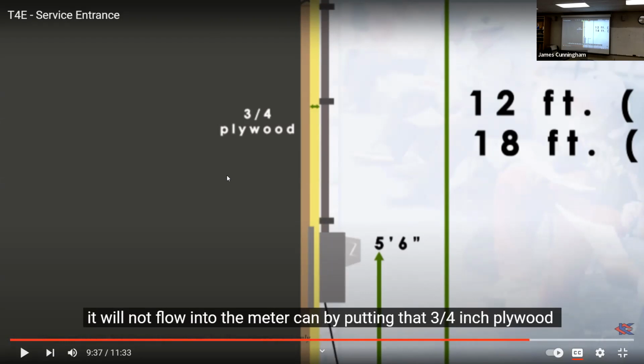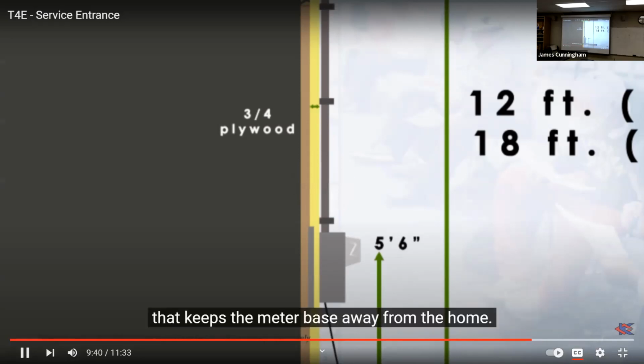It used to be we could stick a sub panel in a closet. Can't do that anymore. It has to be accessible. It has to have 5-foot clearance around it so that you can get access in case of emergency. You see people putting pictures over them and all kinds of stuff. That doesn't meet code. It has to be accessible. A way that keeps the meter base away from the home.